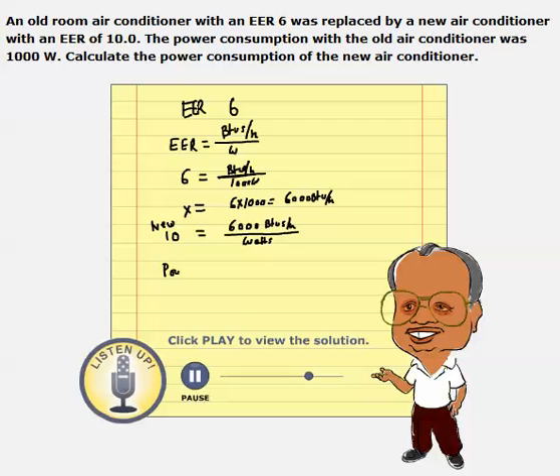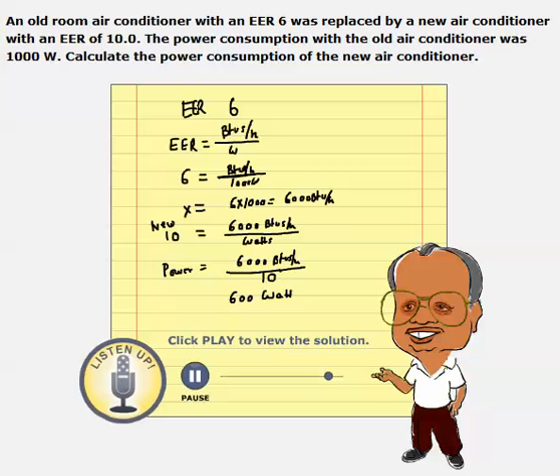To calculate the power, we have a 6,000 BTUs per hour load, and we know the EER is 10. So dividing by this, we get the power, which is 600 watts. By replacing the old air conditioner, which used to consume 1,000 watts, with this new air conditioner that has an EER of 10, we are reducing the power consumption to 600 watts.